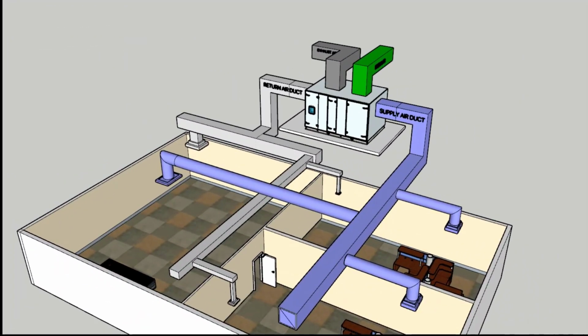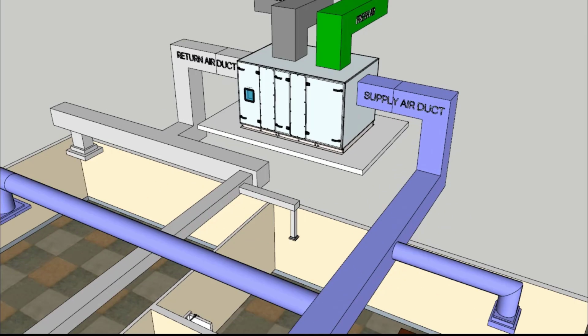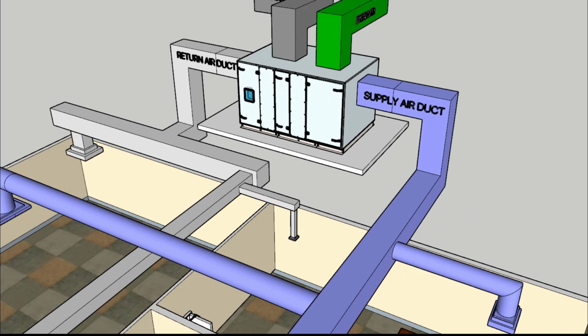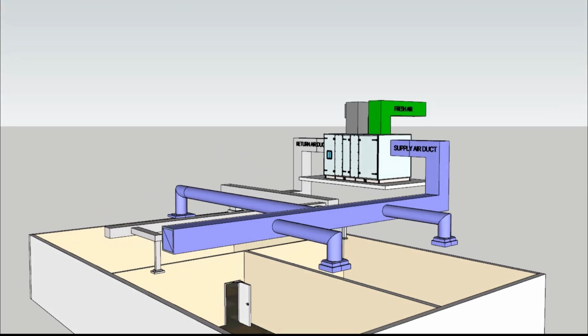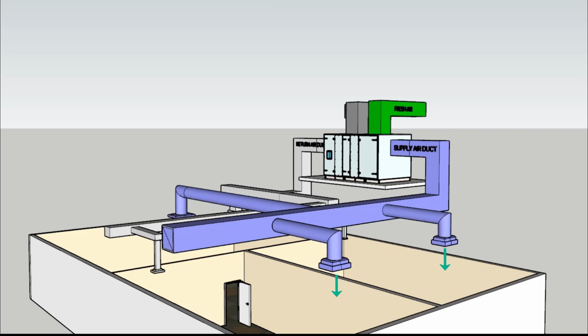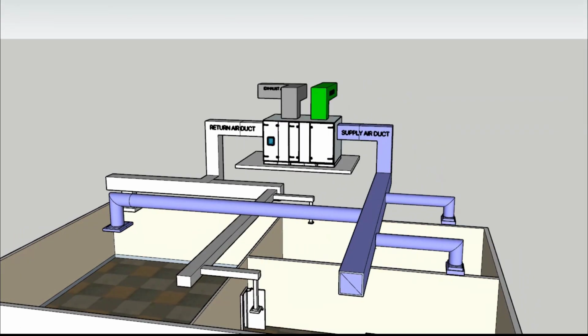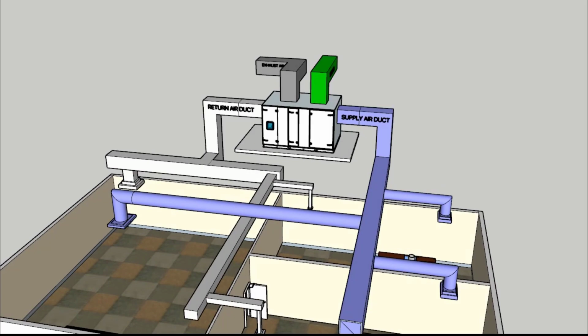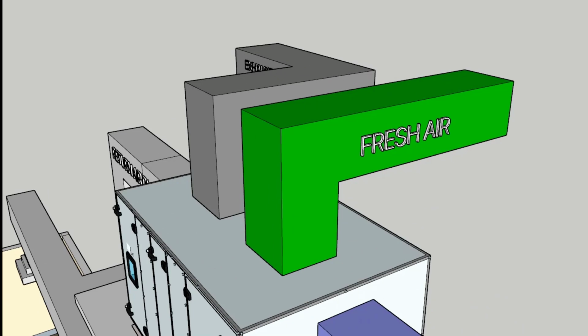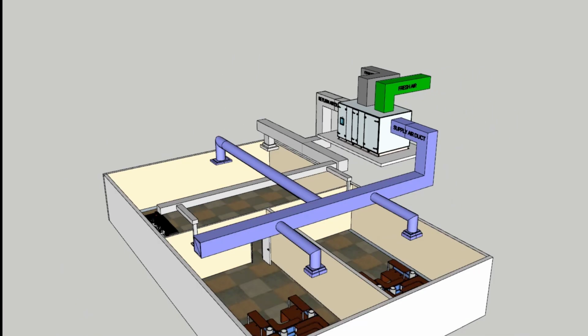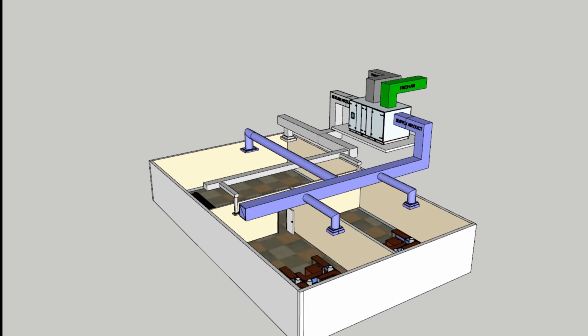Okay, so this is a simple AHU construction that supplies fresh air to a certain space or room. Air handling deals with filtering the indoor air with an air filter. This is the air handling unit from which filtered air is supplied. The temperature of this purified clean air is then adjusted to make it more or less comfortable. To enhance air quality, a portion of the inside air is also partially replaced by new outdoor air during this procedure. Thus, the air from the room will return to the AHU and be replaced with fresh air. That is a brief summary of how an AHU works. With a BMS, we may improve it in the simplest way possible.